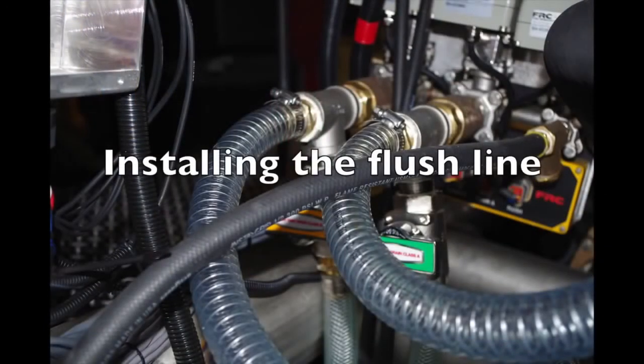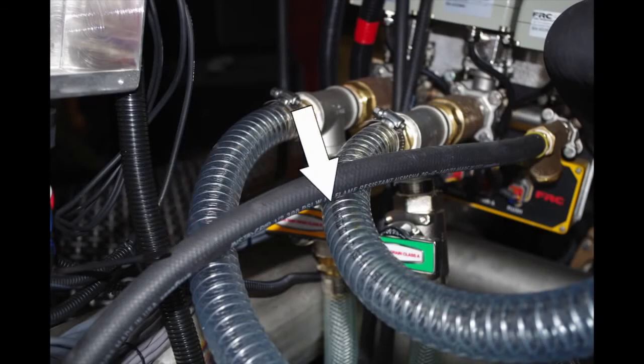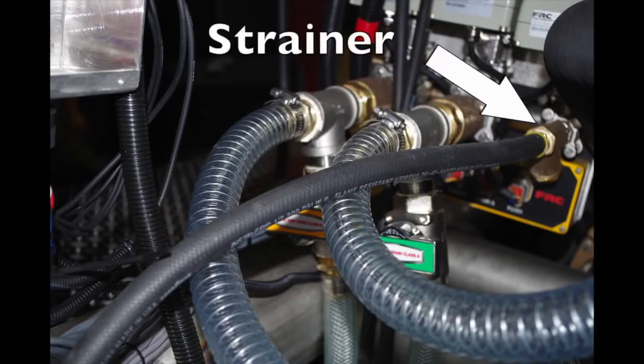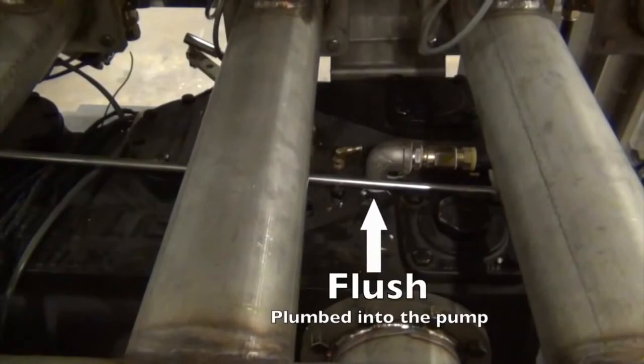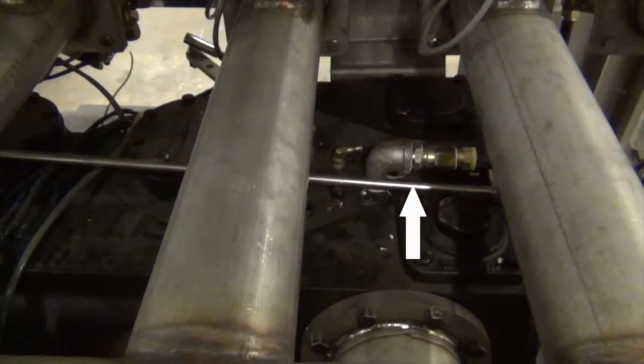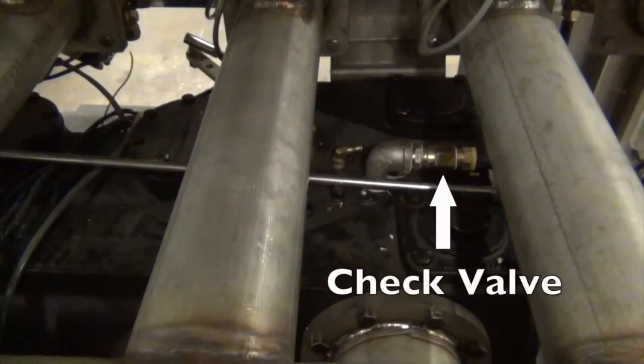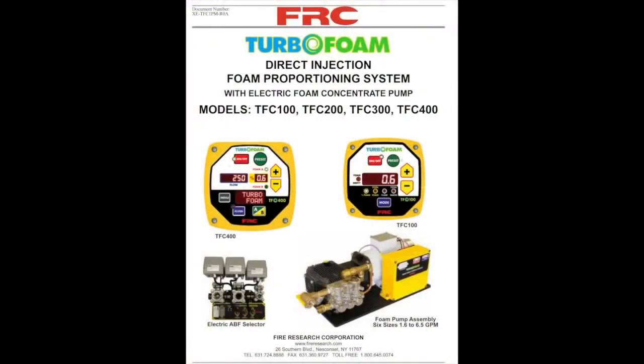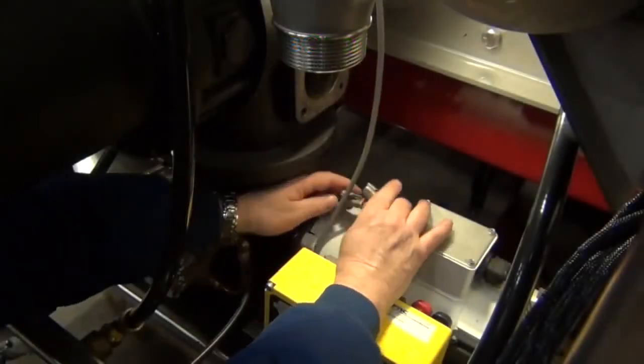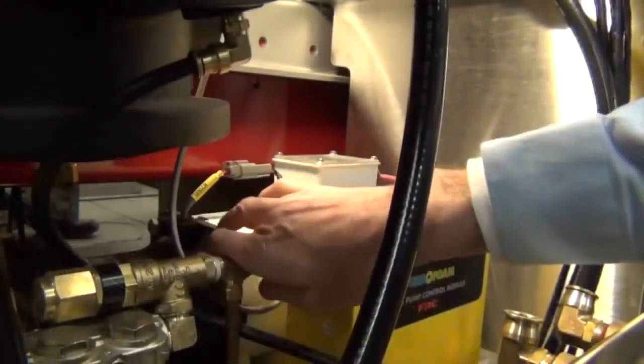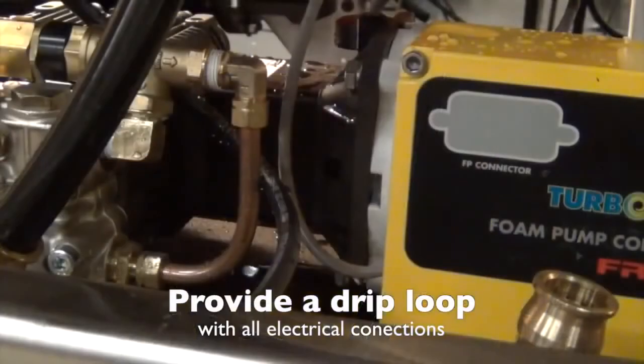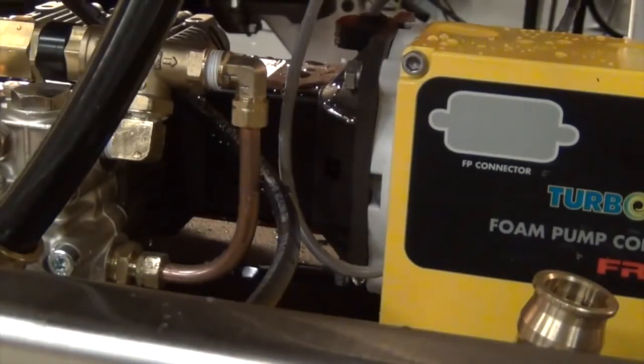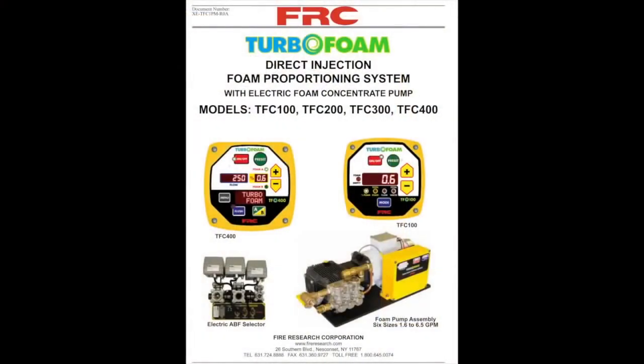Install a flush line that has a minimum inside diameter of 1/2 inch and is rated for at least 500 psi. A strainer is placed in the line before the selector assembly. The flush line is plumbed into the discharge manifold of the pump. The flush line has a check valve in it to prevent foam from being discharged into the pump. For detailed wiring information, please reference the Fire Research Installation Manual. When connecting all wiring, provide a drip loop to help prevent excessive water from running into the electrical connections. For more information on programming and calibrating the TurboFoam system, please view our TurboFoam programming and calibrating presentation.